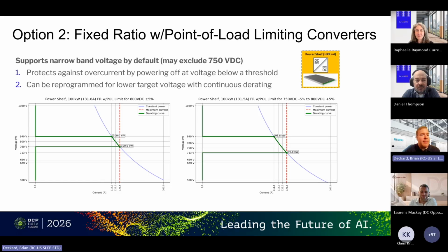What becomes important is to consider that long term, you would have a desire to scale beyond 800 volts potentially in the future, as loads continue to grow and power within the IT rack continues to increase, for the purpose of concentrating parallel operations and achieving peak efficiency of data transfer among parallel processors, avoiding packet loss through conversion to fiber optics and so forth.